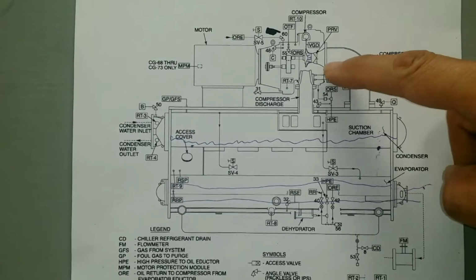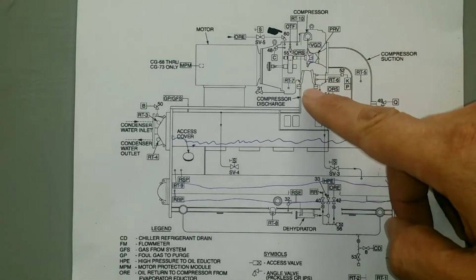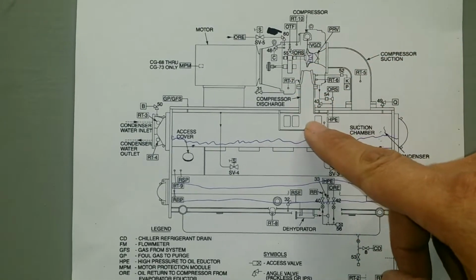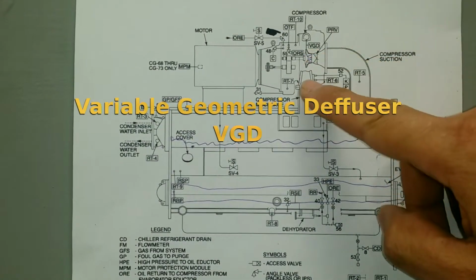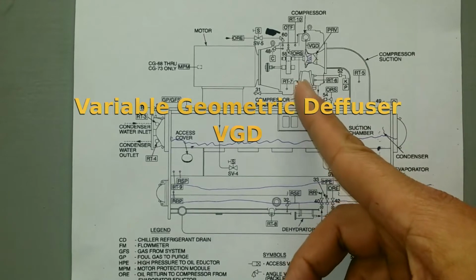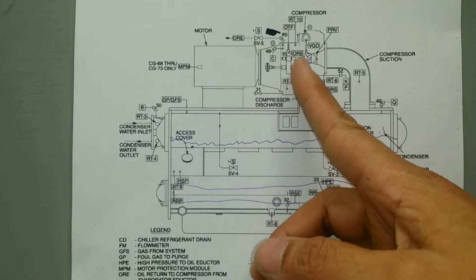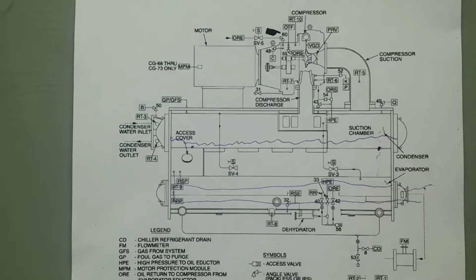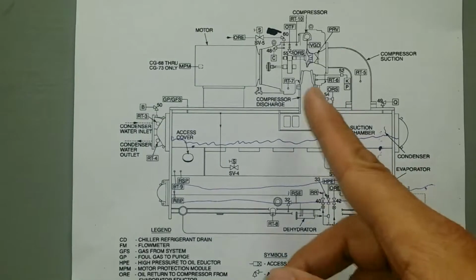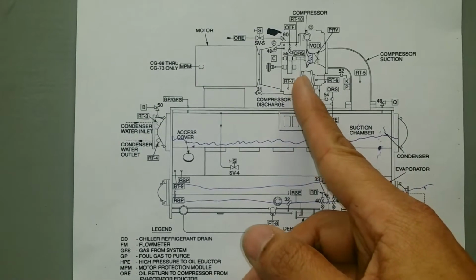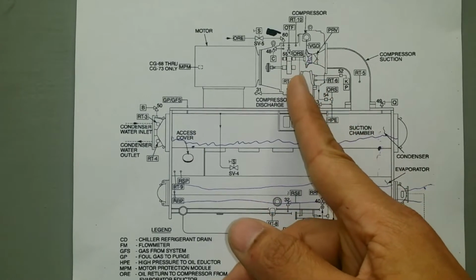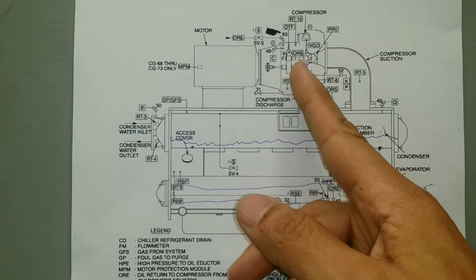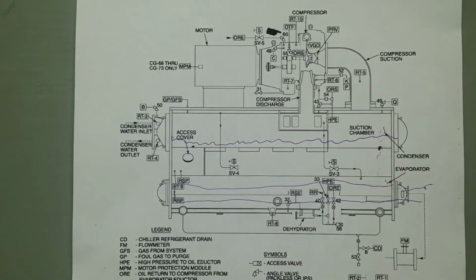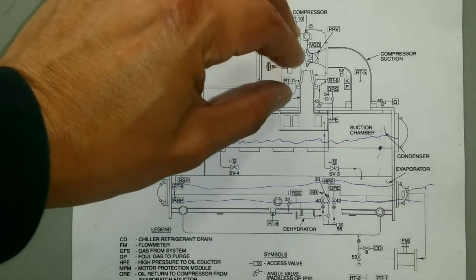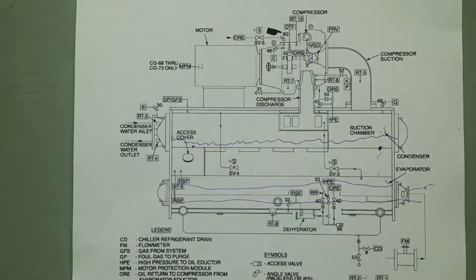Now, that was the suction side of the compressor. On the exit or discharge side of the compressor, you have what is called a variable geometry diffuser, which is a plate that opens and closes, and it limits how much output can come out of the compressor. It is needed there so that whenever there is too much output, it opens more, and whenever there is not enough output, it starts closing. By doing that, it reduces the noise that comes out of the unit.